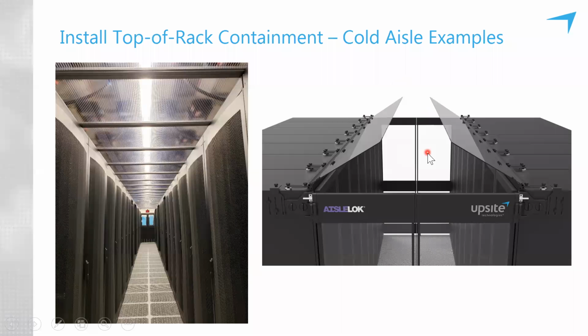And to date, we're not aware of any fire marshals objecting to the baffles blocking the sprinkler spread, as long as the requirement of 18 inches from the top of the baffle to any sprinkler head is maintained. These have been accepted by local fire marshals. The baffles are modular in that there's one baffle for each cabinet, and they are purchased in widths that match the width of the cabinet.